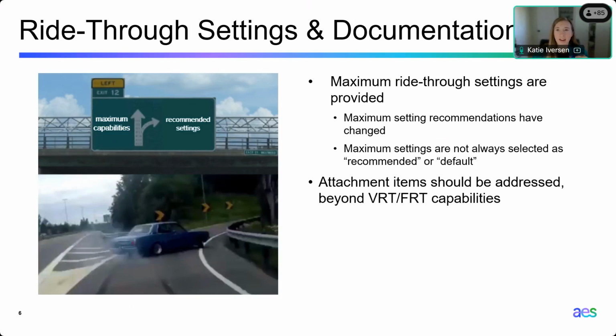I want to note that what I see are maximum ride-through settings provided, or capabilities. Capabilities become settings. The recommendations have changed over the years, and there's good reasoning for that. Once new standards come out, manufacturers should look at their equipment and figure out: do we comply with this one? What tests do we need to do?